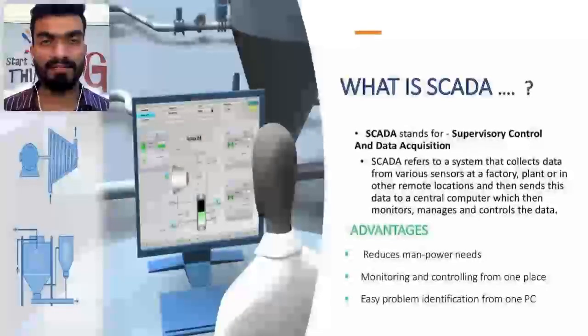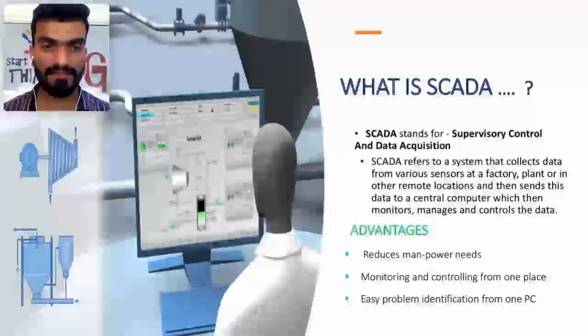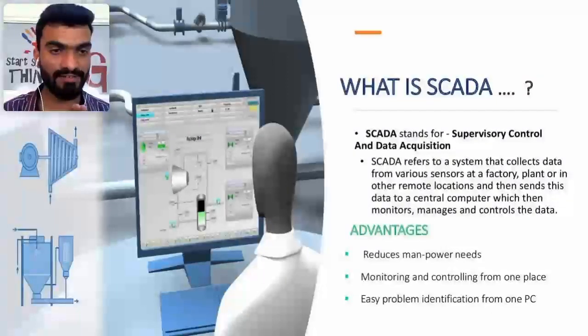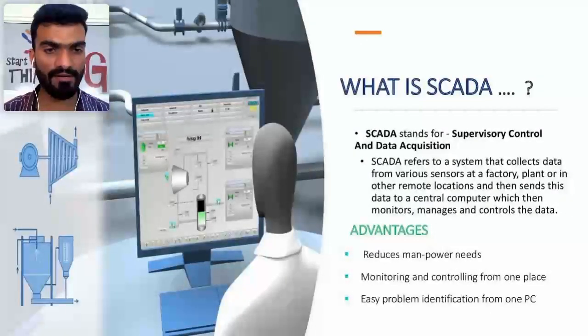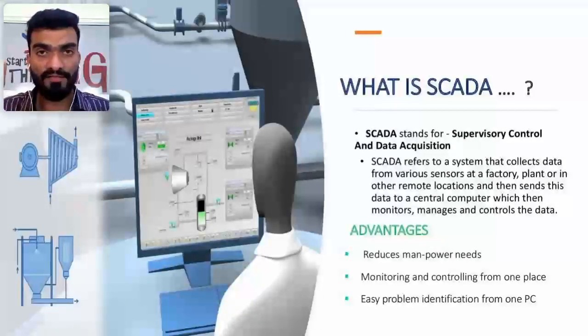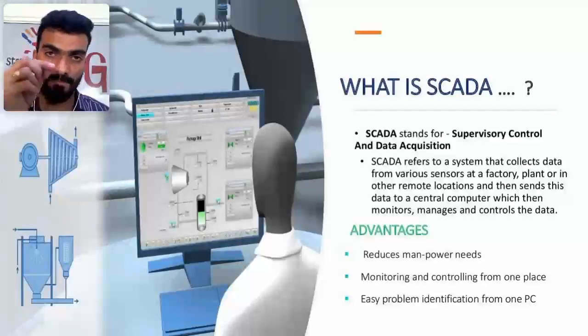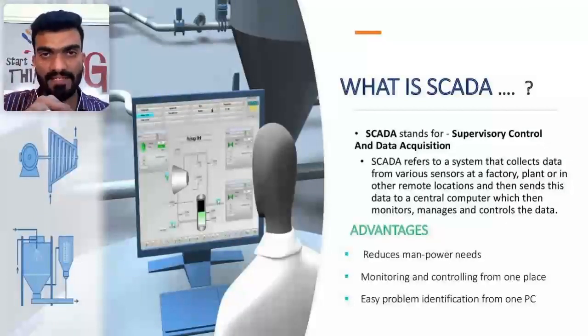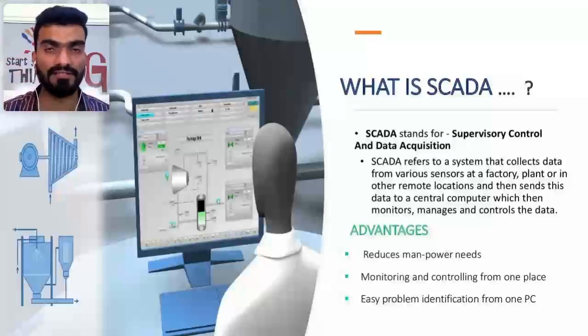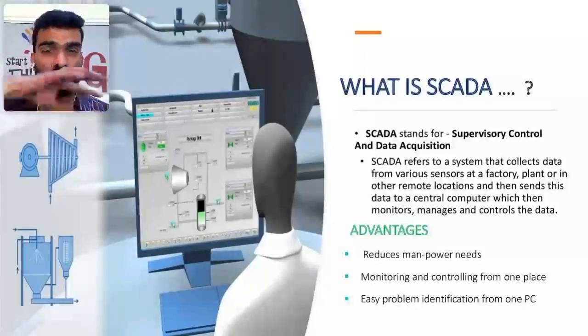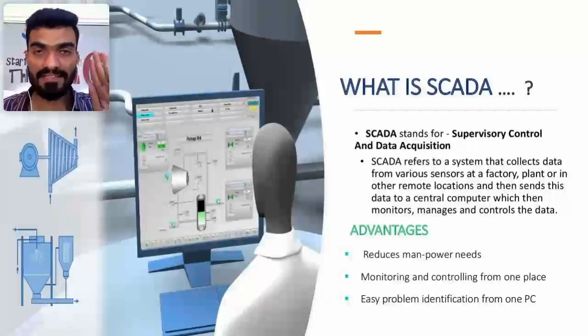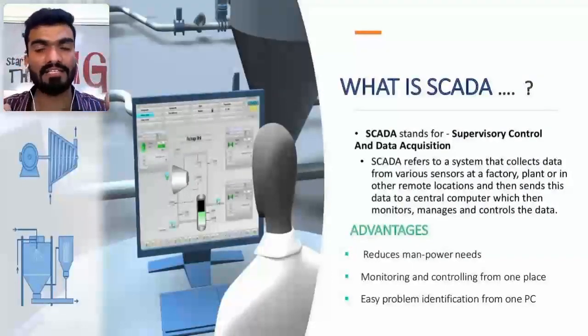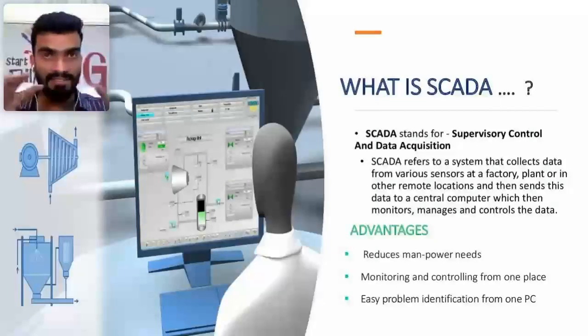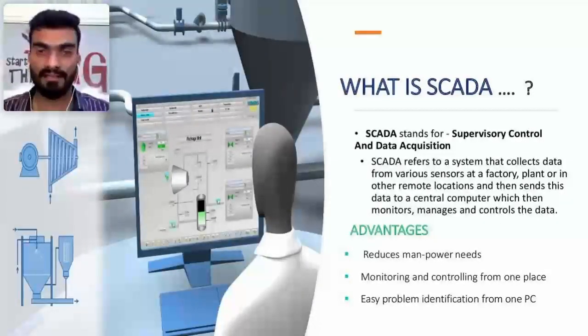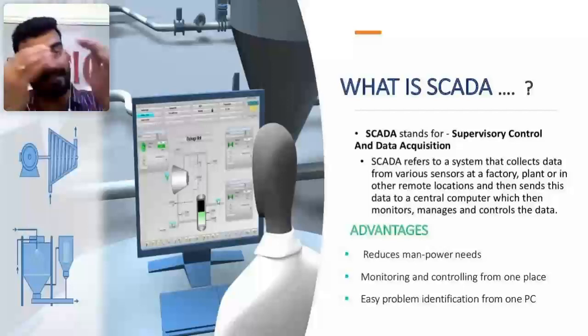Then, what is SCADA? SCADA is like supervisory control and data acquisition. If you see into this screen, we have shown some screen over here. SCADA is basically a software that can be installed into the PC, and through this PC we can connect to the PLC by means of communications. So my SCADA is useful to control the entire plant, whereas HMI is able to control a machine, but SCADA is more scalable. So it's like the controlling will become supervised, and the data can be acquired and stored.